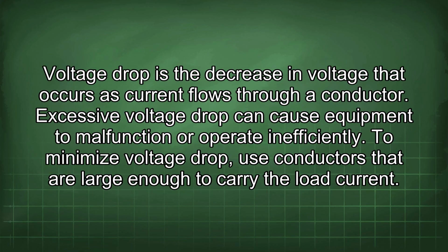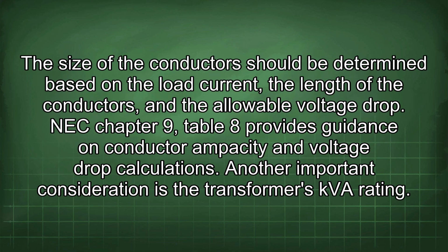Voltage drop is the decrease in voltage that occurs as current flows through a conductor. Excessive voltage drop can cause equipment to malfunction or operate inefficiently. To minimize voltage drop, use conductors that are large enough to carry the load current. The size of the conductors should be determined based on the load current, the length of the conductors, and the allowable voltage drop. NEC Chapter 9, Table 8 provides guidance on conductor ampacity and voltage drop calculations.